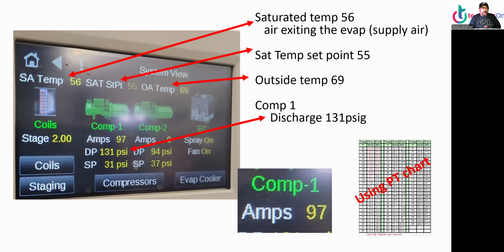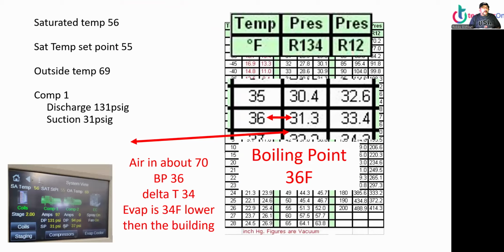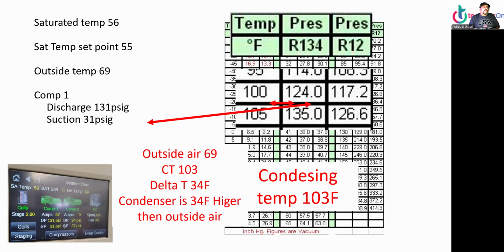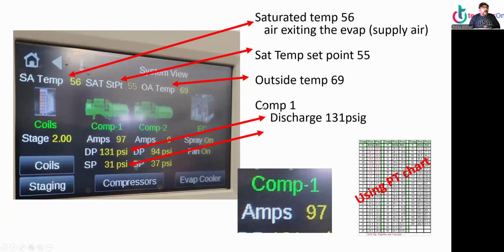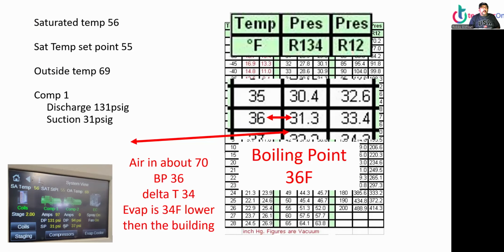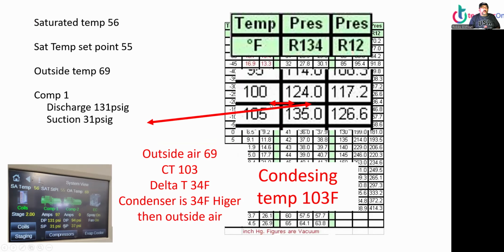And compressor 1 discharge 131. And suction pressure 31. Using a PT chart, boiling point is 36, all righty? Because we know pressure is 31, 31 equals 36 temperature. Correct, boiling point should be 36 in air conditioning. So air is about 70 degrees, boiling point 36, that's a delta T of 34, evaporator 34 degrees lower than the building. Excellent. Outside temperature 69, condensing temperature 103, delta T is 34, condensing temperature 34 higher than the outside air. Okay, sounds right. It says here, back here, discharge PSI 131. The discharge PSI 131 is about 102, 103.